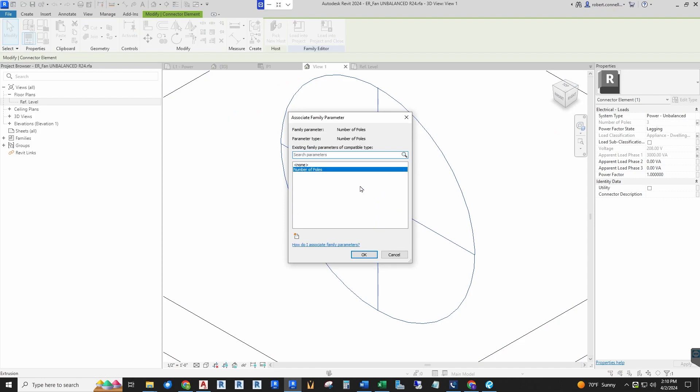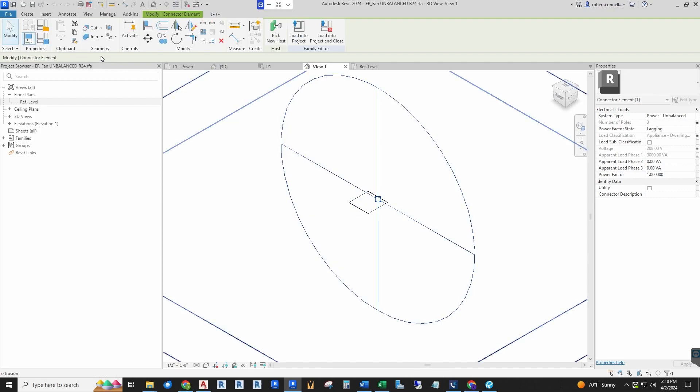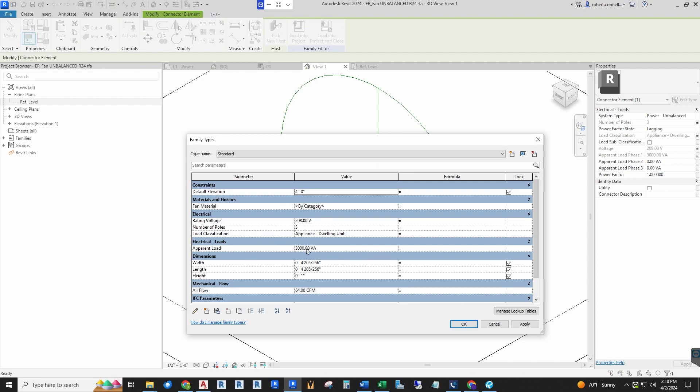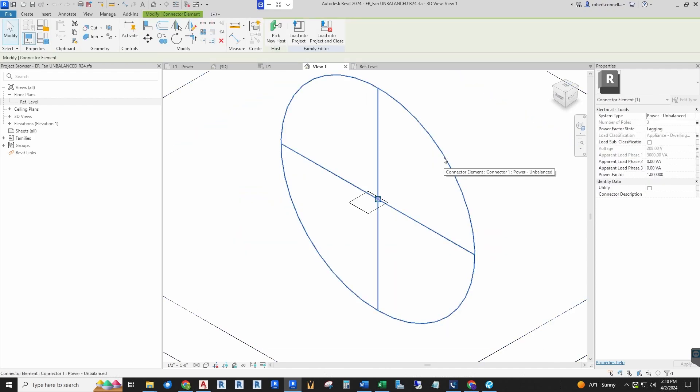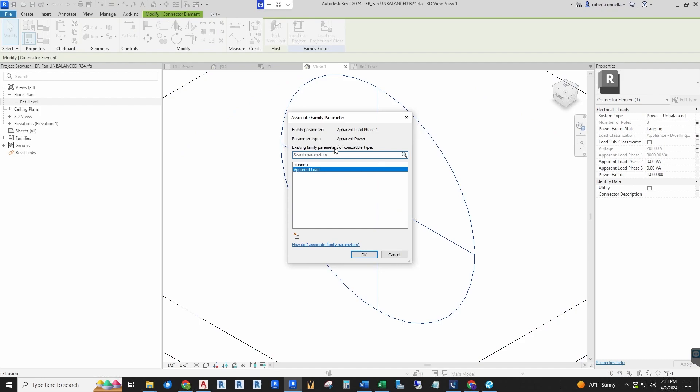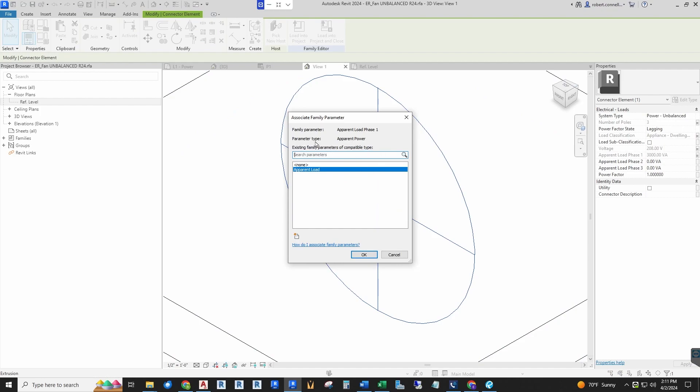I call it mapping a parameter to the type, or you can say associating a family parameter to the type. If we click that, it is attached to number of poles. If we go up to the family types, you will see number of poles, the load classification, the voltage, and apparent load. This apparent load is only reporting phase 1 as the apparent power.